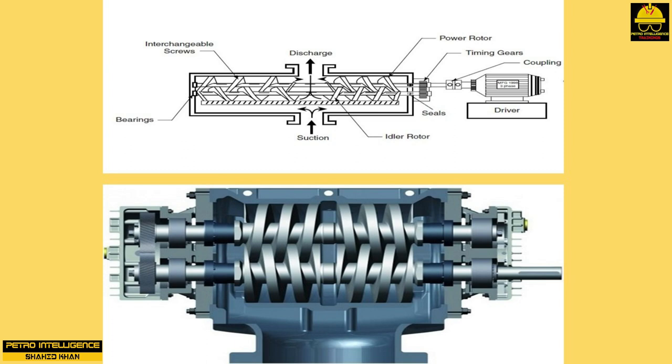This feature makes it an ideal choice in tank stripping operations or in operations in which fluid suction pressure will vary. The twin-screw pump has a driving and a driven shaft, two screws, an external set of timing gears and heavy-duty bearings, and divided entry flow as shown in picture. As fluid enters the pump, it is divided into two equal streams and directed to the two ends of the shaft. The pumping action of the screws moves the two streams of process fluid in a straight line between the closely spaced rotors until they combine at the discharge port.